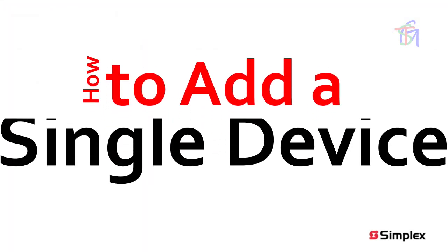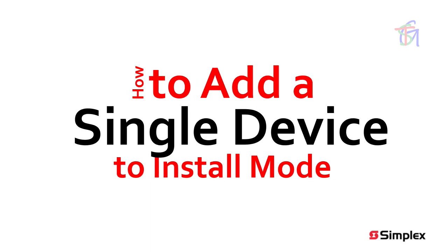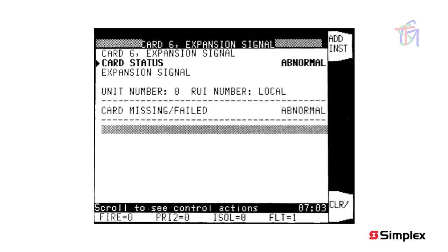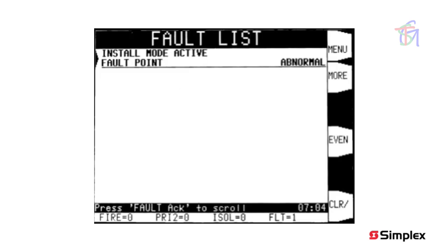Devices can be added individually to the install mode list. Note that this requires being logged in at level 3. The example fault list shows a fault from a missing slave card in the panel. If necessary, move the highlight on the display to the missing card using the up, down, page up, or page down keys. Press the more soft key for more info. Move the highlight down to the card status line, and a soft key option 'add' will appear. Pressing this soft key will add this point to the install mode list and display an accepted screen briefly. Pressing the fault acknowledge key will show the fault list, now with a single entry.